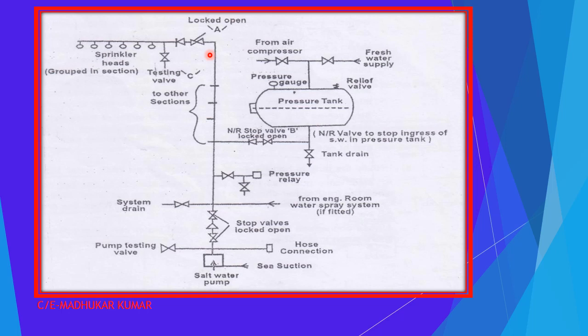Okay, so in these valves, this is the complete section. We have the sprinkler heads which are installed in the section. This is testing valve C. Testing valve C is basically utilized for the purpose of testing the alarm of that particular section. If we open that, then water starts flowing into this, and we will see how the alarm also works. So that will give you the audio visual alarm for that particular section. So we can test without operating the heads.